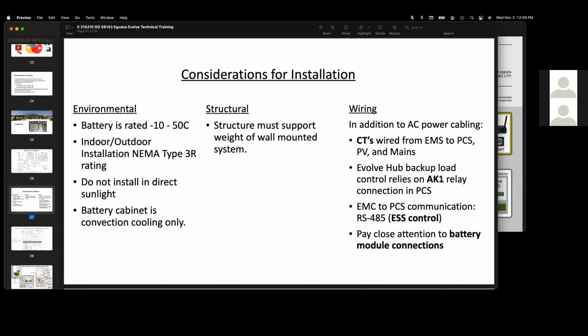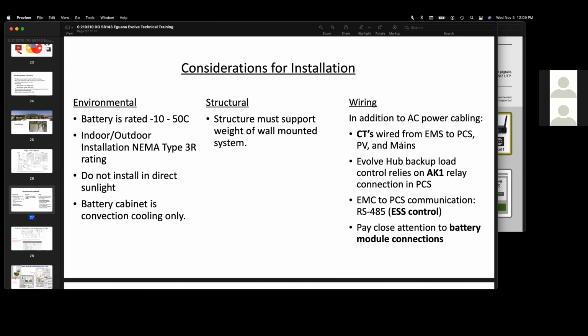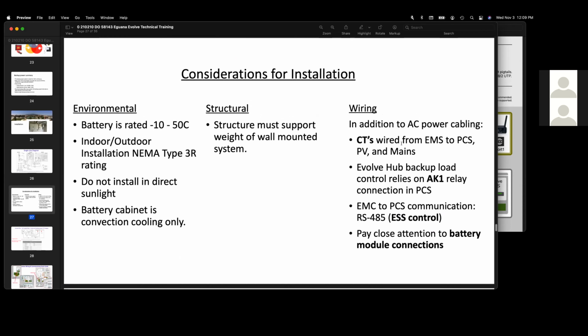As far as the AK1 relay connection, this cable, I believe, is maybe 15 to 20 feet long. It comes with each system, but if you install the hub as instructed in the manual, directly to the left of the PCS cabinet, you will not have to extend that. So the only additional wiring you may need to plan on is CT extension wires, and you can get that specification from our installer resources package. I believe if Courtney can share that with you, the CT extension specs are shown in there. Thank you for your question, Parker.